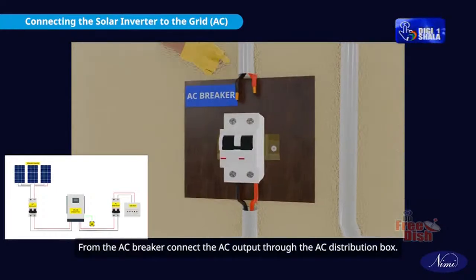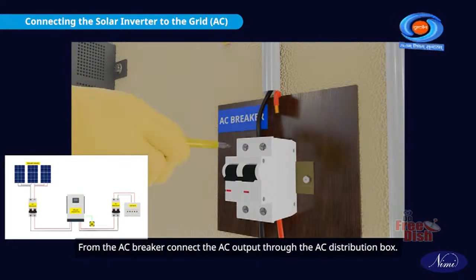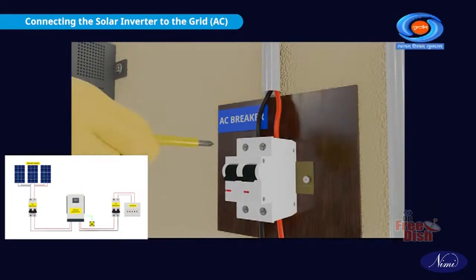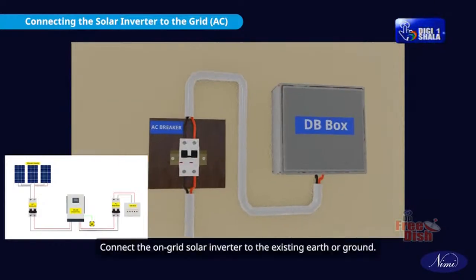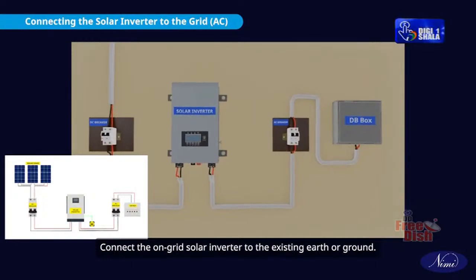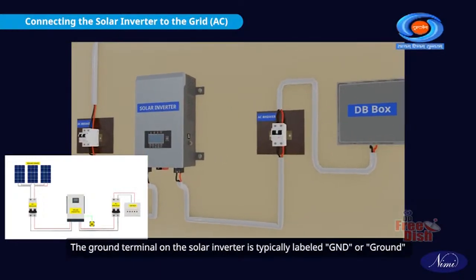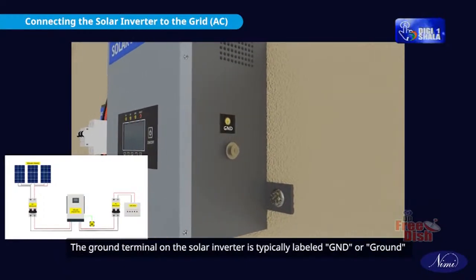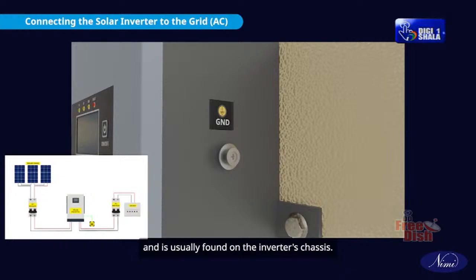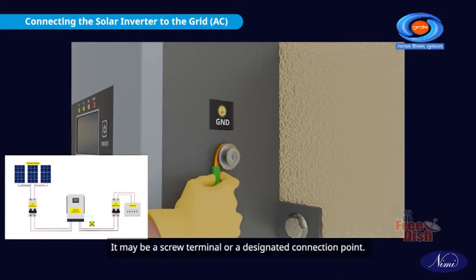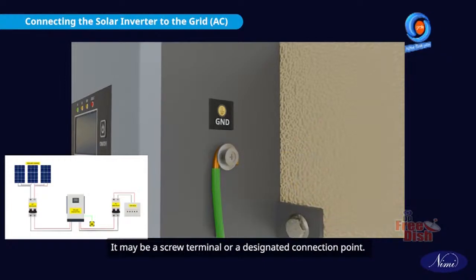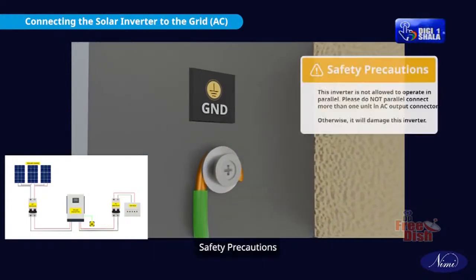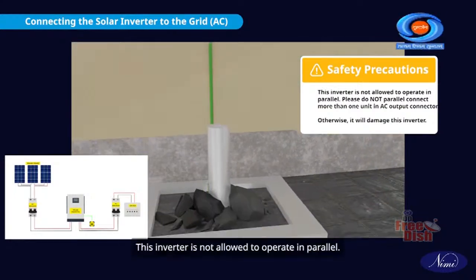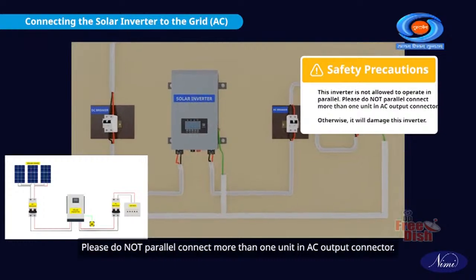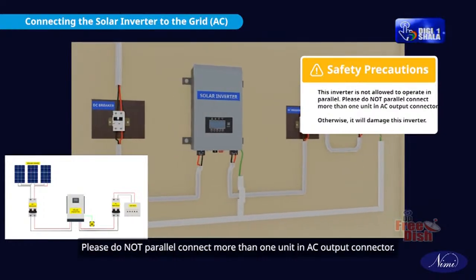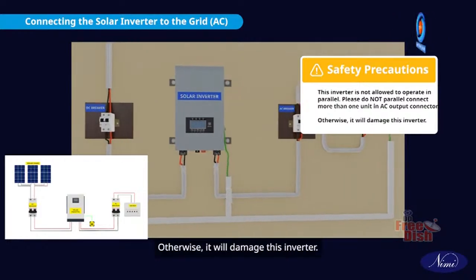From the AC breaker, connect the AC output through the AC distribution box. Connect the on-grid solar inverter to the existing earth or ground. The ground terminal on the solar inverter is typically labeled GND or ground and is usually found on the inverter's chassis. It may be a screw terminal or a designated connection point. Safety precautions. This inverter is not allowed to operate in parallel. Please do not connect more than one unit in parallel at the AC output connector, otherwise it will damage this inverter.